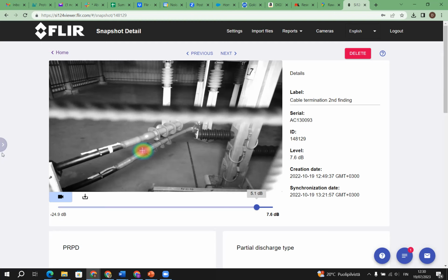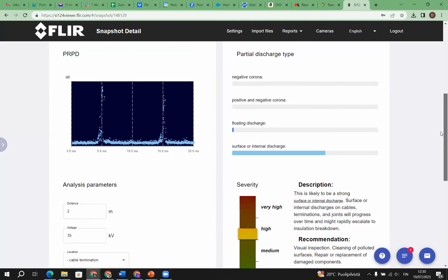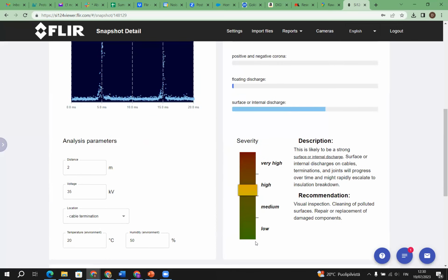And we actually found this. These are cable terminations in the substation inside. And the criticality assessment was quite worrying. It's a surface internal discharge on cable terminations, only 35 kilovolts, but still high severity. As you can see, there is likely a strong surface internal discharge on cable terminations and joints that will progress over time and might rapidly escalate into a breakdown of the insulation. So basically it's telling that they need to clean.